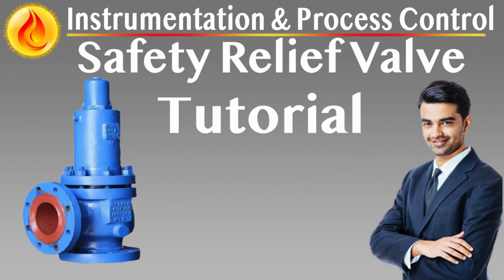Balanced bellows relief valves: use when built-up back pressure exceeds limits for non-balanced types. Back pressure is less than 65%, preferably 50%, of set pressure. Bellows are vented continuously and routed to safe areas. Suitable corrosion-resistant bellows material is required. An auxiliary balancing piston may be necessary if freezing or leakage risk exists. Avoid use in freezing environments, reciprocating compressor discharge, or fouling or coking services where bellows may become damaged or blocked.